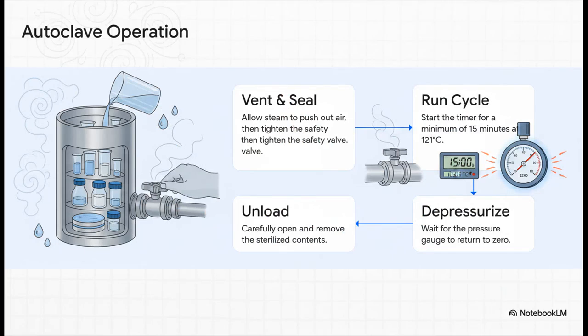So, putting it all together, here's how it works. You add some water, you load your stuff, and you let the first blast of steam push all the air out before you seal it tight. Then you run it at our magic numbers, 121 degrees for 15 minutes. And listen, the most important part, for safety's sake, is you wait until that pressure gauge is back at zero. Don't even think about opening that door before then.